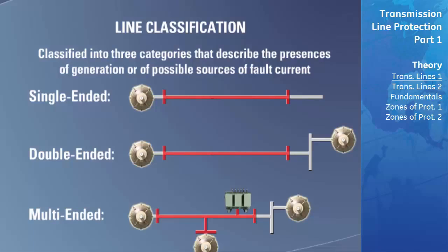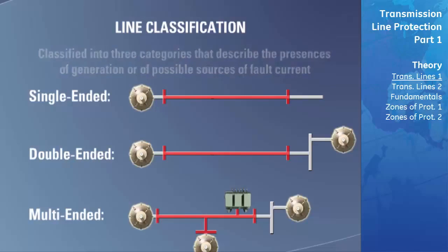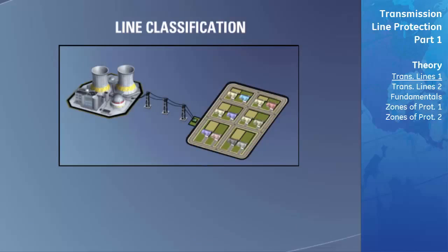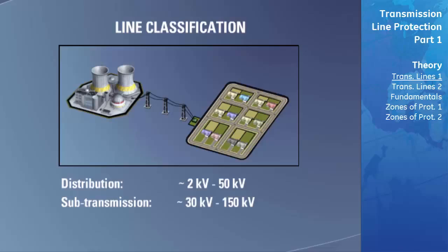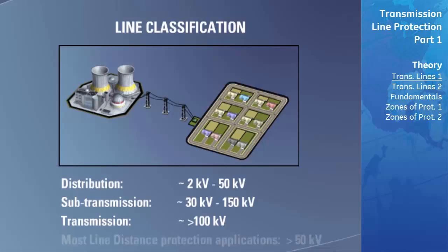Sometimes the transmission line itself will be tapped to provide a source of power to a load. Distance protection is one method of protecting a transmission line in this configuration and will be covered in detail later. The voltages used for transmission are split into three categories: distribution levels, in the range of 2 kilovolts to 50 kilovolts; sub-transmission levels, in the range of 30 kilovolts to 150 kilovolts; and transmission levels, which are greater than 100 kilovolts. Most applications using distance protection are 50 kilovolts or greater.